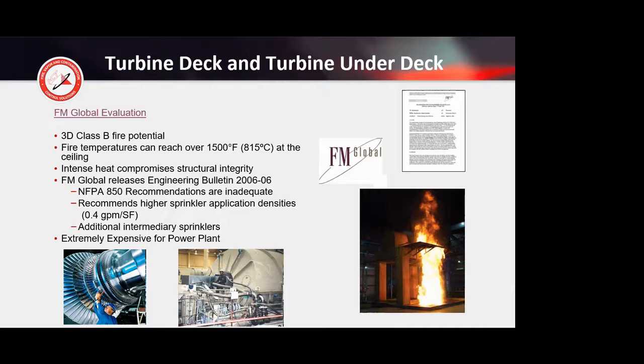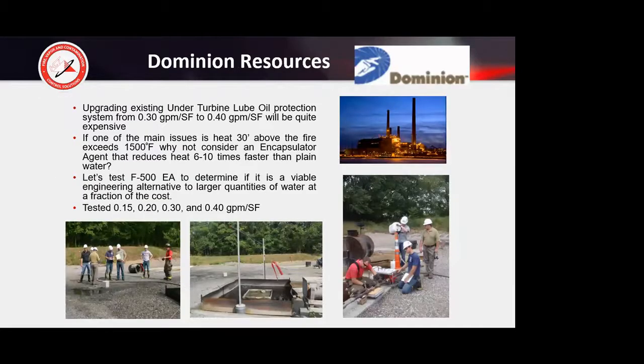We worked with a couple of our customers in the industry. Here's Dominion Power. They're the third or fourth largest energy provider in the United States. And that's what they were saying: if we have to upgrade our under turbine lube oil fire protection systems, which are just plain water, and we know water is not very effective, from 0.3 to 0.4, that's going to be quite expensive. And it goes, if one of the main issues is heat 30 feet above the fire exceeds 1,500 degrees, why shouldn't we consider your F500 encapsulator agent, which we know reduces heat 6 to 10 times better than plain water? So that was the concept of how we got involved in this particular application.